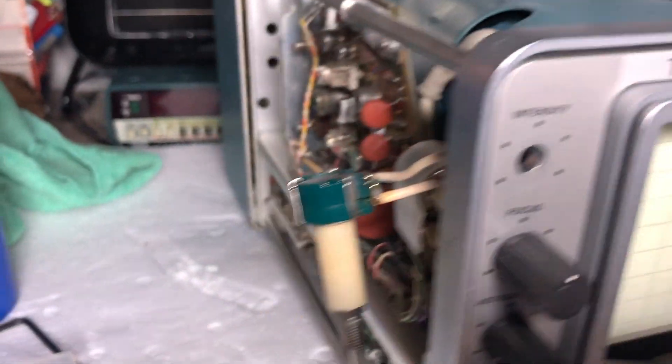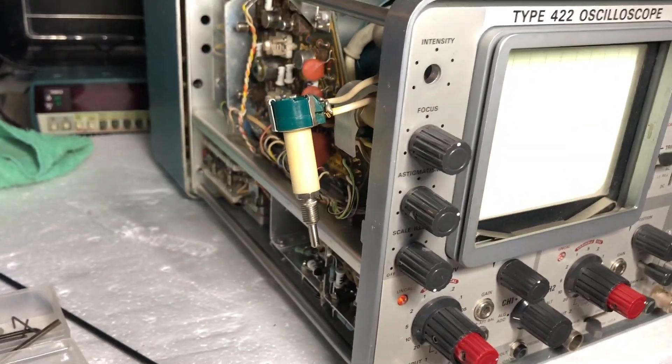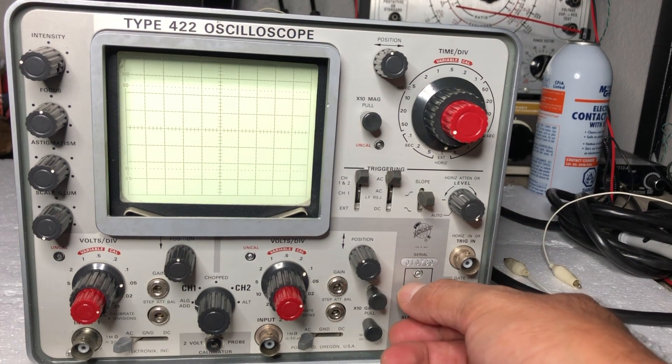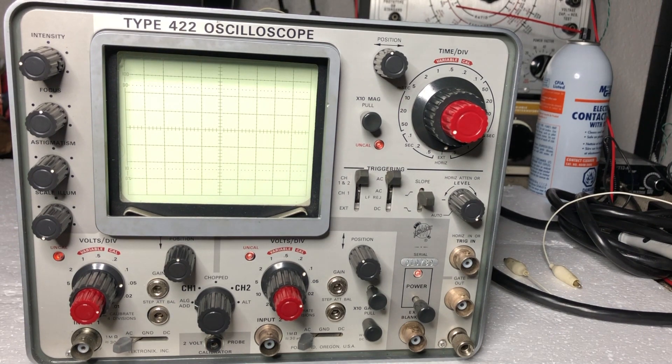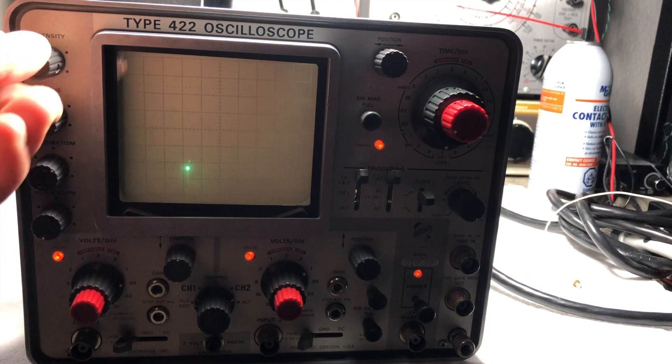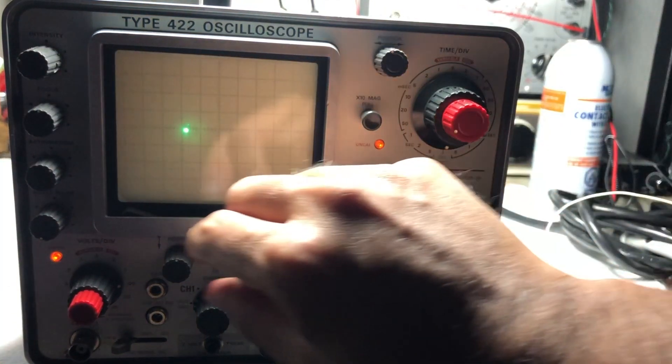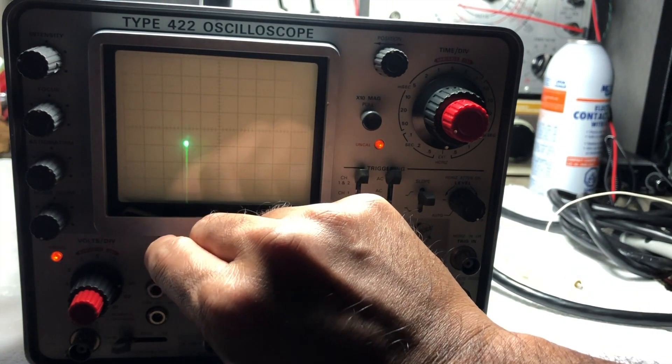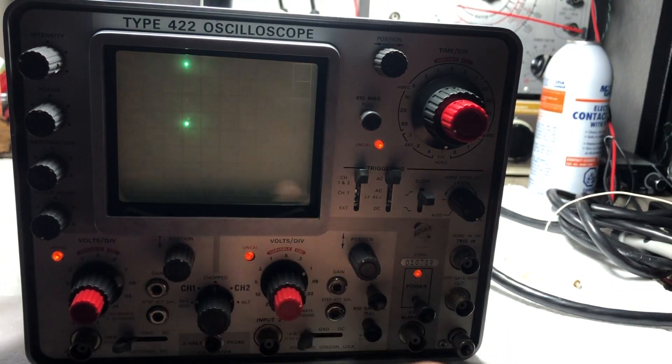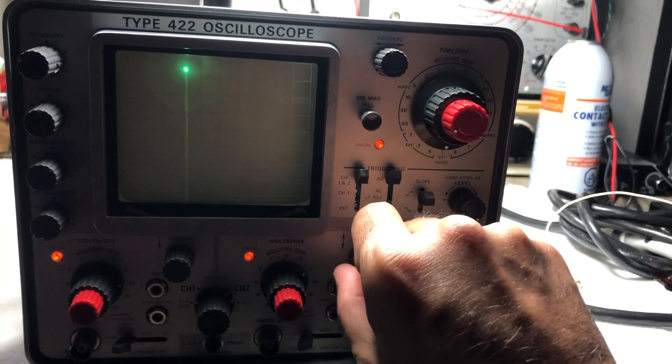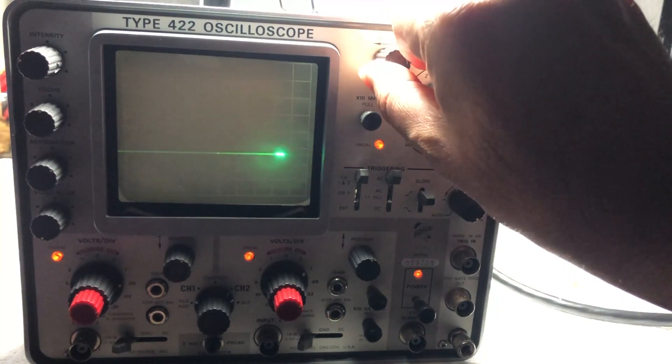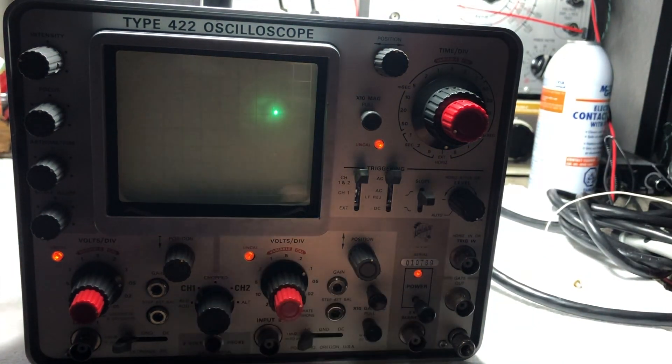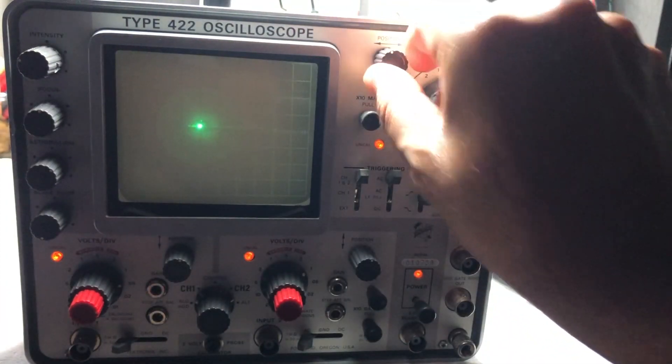That's for channel one. That's for channel two. That's for channel one. That single pot was the one which was driving us nuts. I'm gonna put it back and then we will continue. Okay, everything is put back in place, and let's power up. Let me cut the light so you can see what's happening with the beam. That's coming up. I have vertical position control for channel one. I have vertical position control for channel two, which is good. I have horizontal position control, which is also good. Let me switch this back to channel one and move the horizontal position.